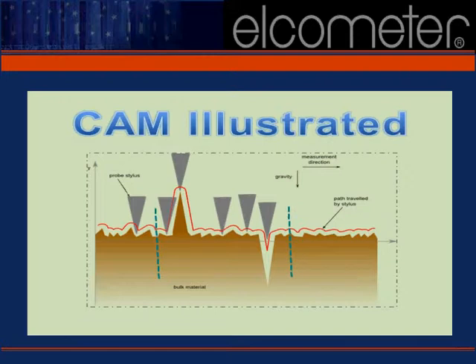Look first at the five reading points in this area. Calculating the average profile using the normal mode, we would have four measurements essentially within plus or minus 1% of each other, with the fifth being relatively high — perhaps high enough to claim its place as the highest reading within this batch. Using CAM, however, the four nearly identical measurements would work to counter this high reading and offer a truer quantitative value for this region.